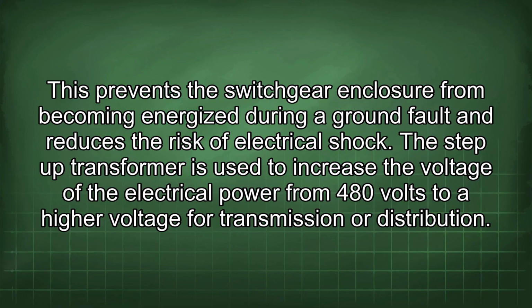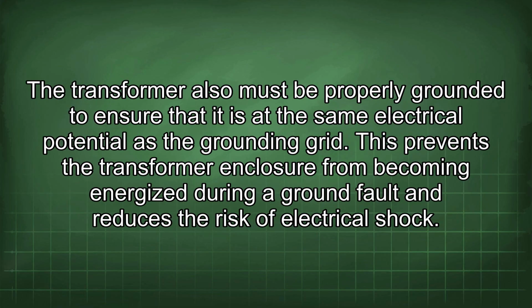The step-up transformer is used to increase the voltage of the electrical power from 480 volts to a higher voltage for transmission or distribution. The transformer also must be properly grounded to ensure that it is at the same electrical potential as the grounding grid. This prevents the transformer enclosure from becoming energized during a ground fault and reduces the risk of electrical shock.